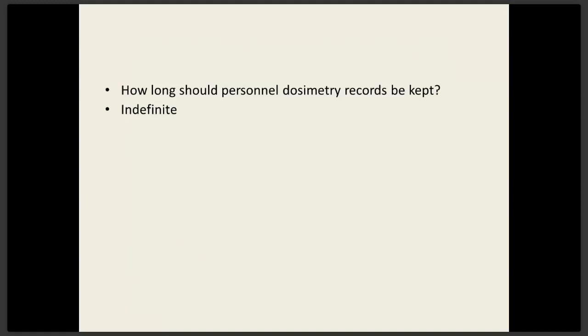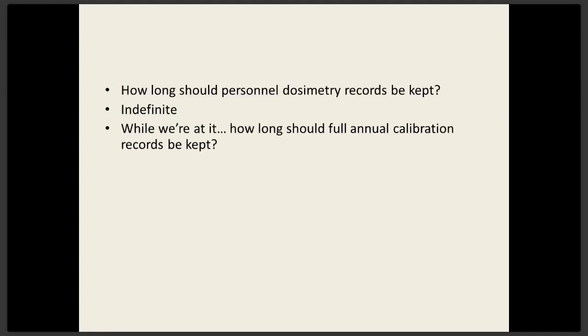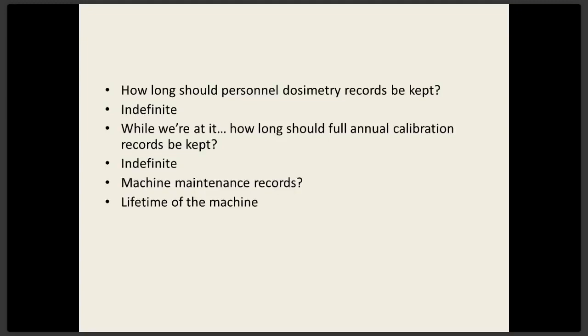And individual workers should know how much radiation they've gotten in their lifetime. Sometimes if a department closes up, the state will actually want to take custody of those records and put them in an archive somewhere. So conventional thinking on radiation records, keep them indefinite, and full annual calibrations of linear accelerators, cobalt machines, those should also be kept indefinitely. Machine maintenance records, lifetime of the machine, and then they can be destroyed.